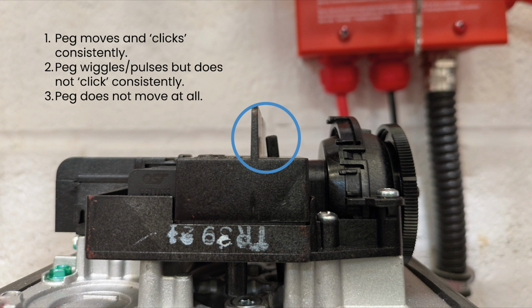Number 3. The pin does not move at all. This could indicate an electrical or mechanical issue with the pump, or a mechanical issue with the flow switch. Venting is still recommended in the first instance, but it is likely that further investigation will be required.